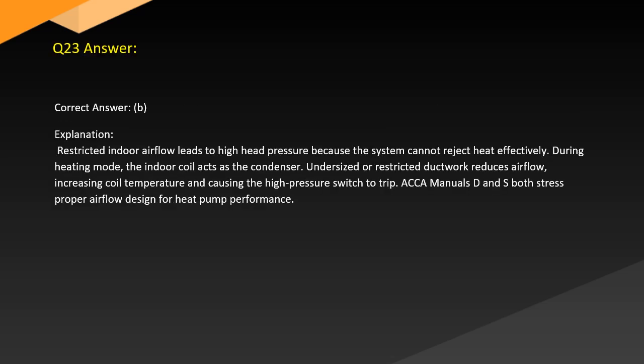Answer. Correct answer, B. Explanation. Restricted indoor airflow leads to high head pressure because the system cannot reject heat effectively. During heating mode, the indoor coil acts as the condenser. Undersized or restricted ductwork reduces airflow, increasing coil temperature and causing the high pressure switch to trip. ACCA Manuals D and S both stress proper airflow design for heat pump performance.